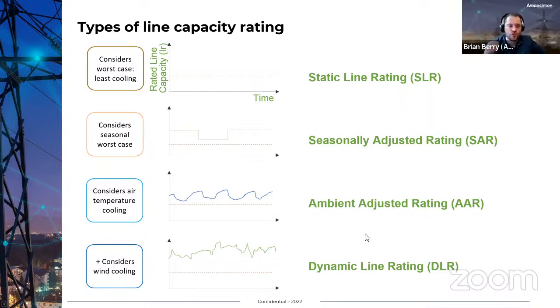But we can take it one step further and use weather providers. We can take weather information, just like on your cell phone telling you whether it's safe to go to the beach, whether it's going to rain, what temperature it's going to be. We can use that to adjust the line rating based on the ambient temperature that's going to exist. So here you can start to see a daily trend, sun comes up, sun goes down.